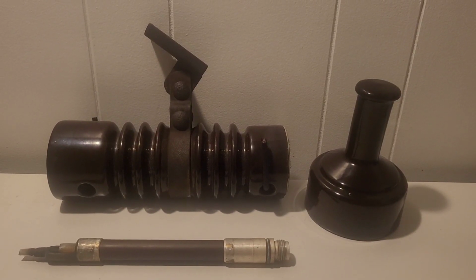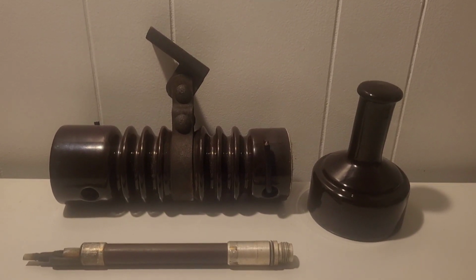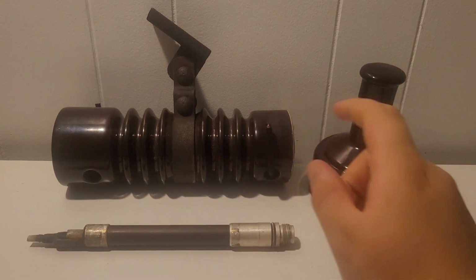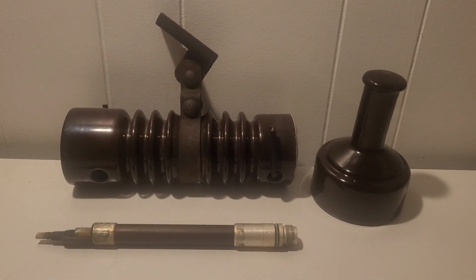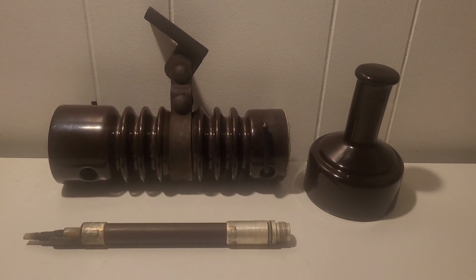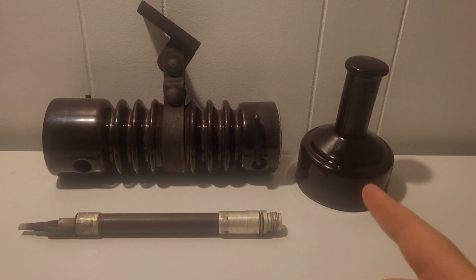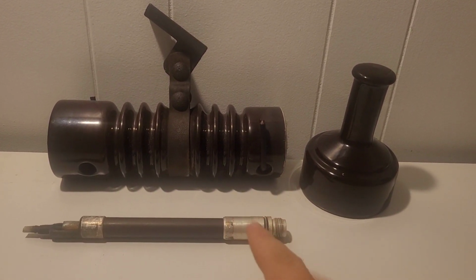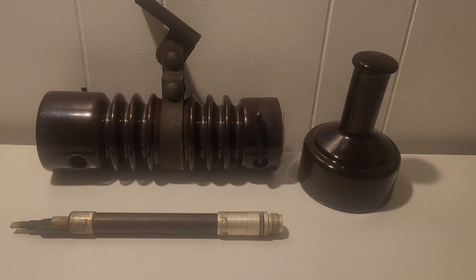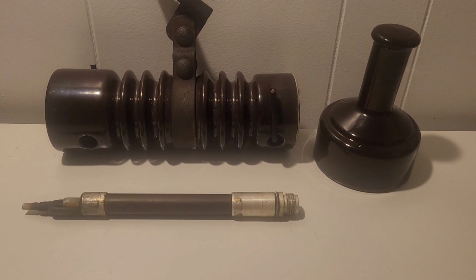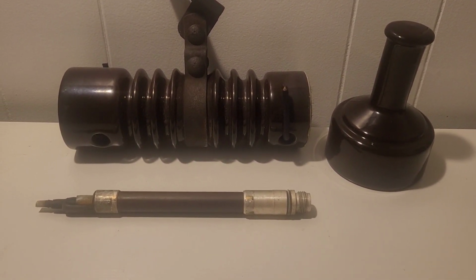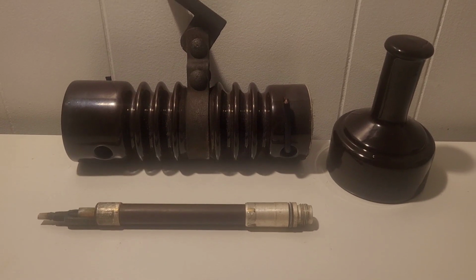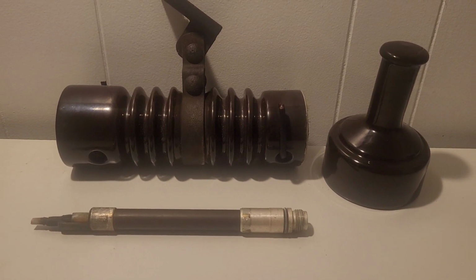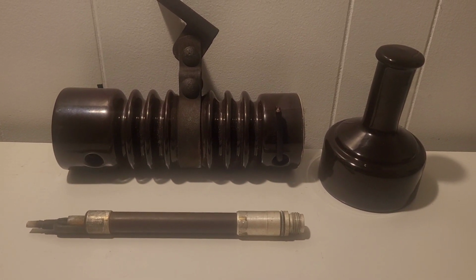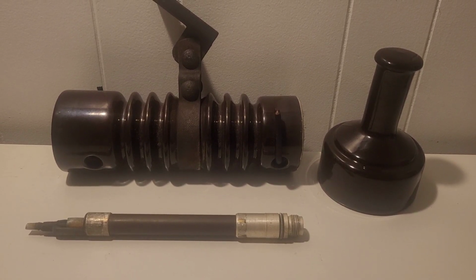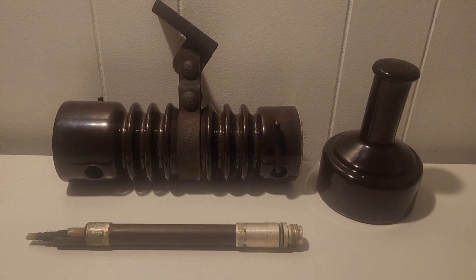With a certain degree of force, you start to understand why it's called the bayonet fuse. You pull that head out of the body like a sword from a scabbard. Once that's out, the head and the fuse are connected. You can unscrew that fuse, and now you get a glimpse of a 6,000 volt fuse on a 4,800 volt distribution line, not a transmission line. We'll get to that in a moment. That's what blows in case there's a high current failure.